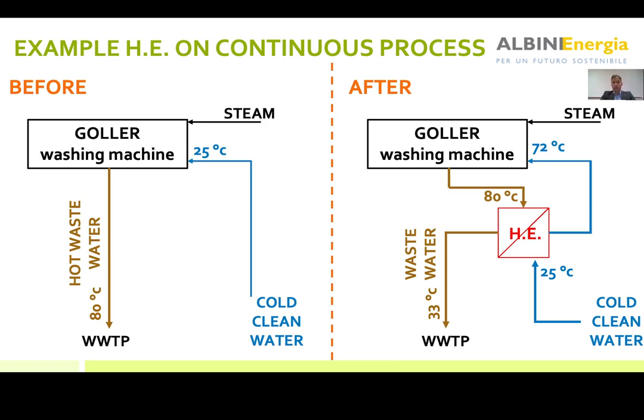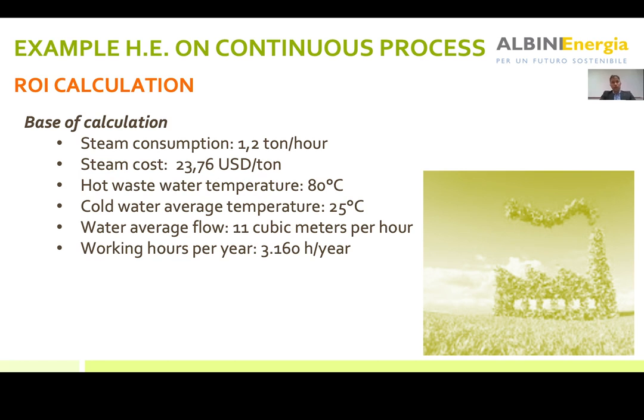With such hot temperature in the fresh water, the steam consumption was significantly reduced with big savings in terms of money. Steam consumption before the intervention was around 1.2 tons per hour and the steam cost in the factory was 23.76 US dollars per tonne. The hot wastewater temperature was 80 degrees, the cold water average temperature was almost 25 degrees.